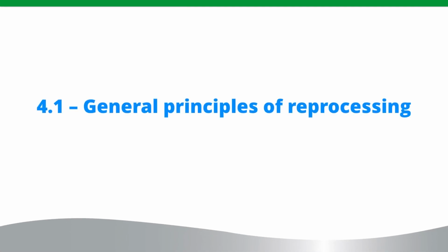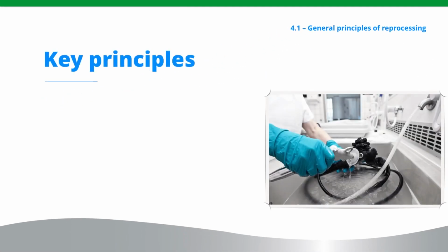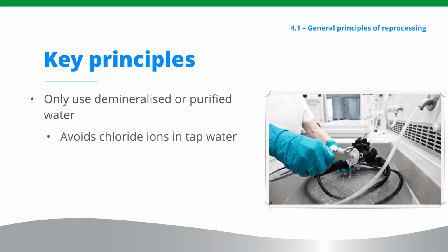section. All items for disinfection should first be cleaned and rinsed, but instruments need special care. All instruments need pre-cleaning and should be submerged in the cleaning solution while scrubbing to remove all traces of previous use. It is important to use demineralized or purified water in the dilution and rinsing processes, especially for expensive endoscopic instruments. We'll take a more detailed look at endoscopes later in this section. The reason we use demineralized or purified water is because tap water contains chloride ions, which can corrode the surfaces and interior areas of these instruments.